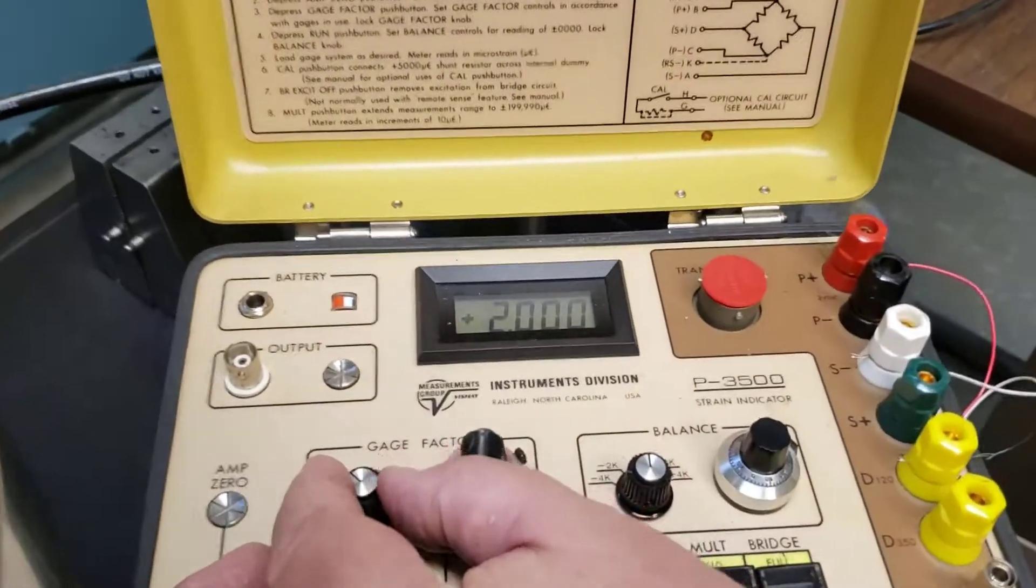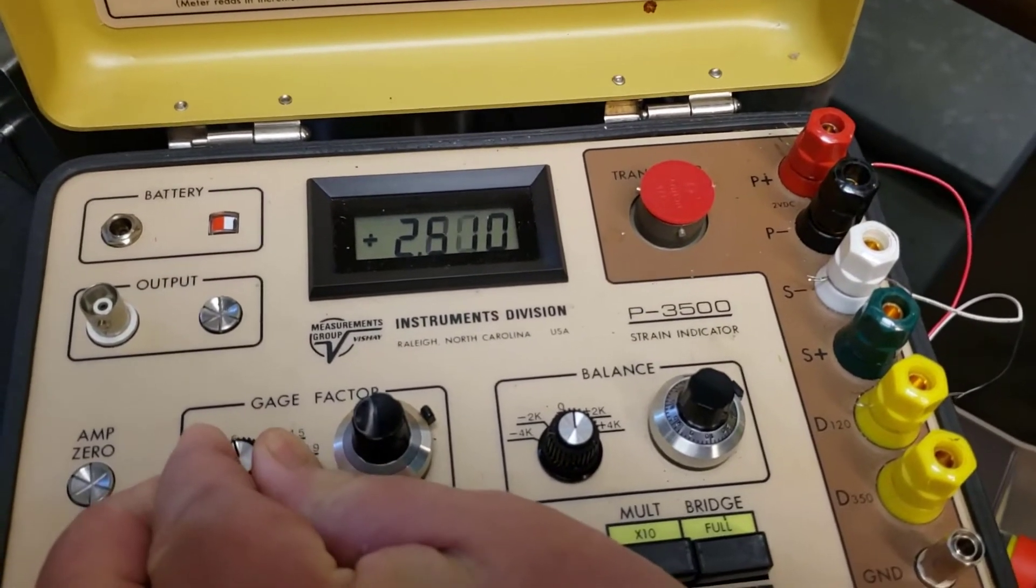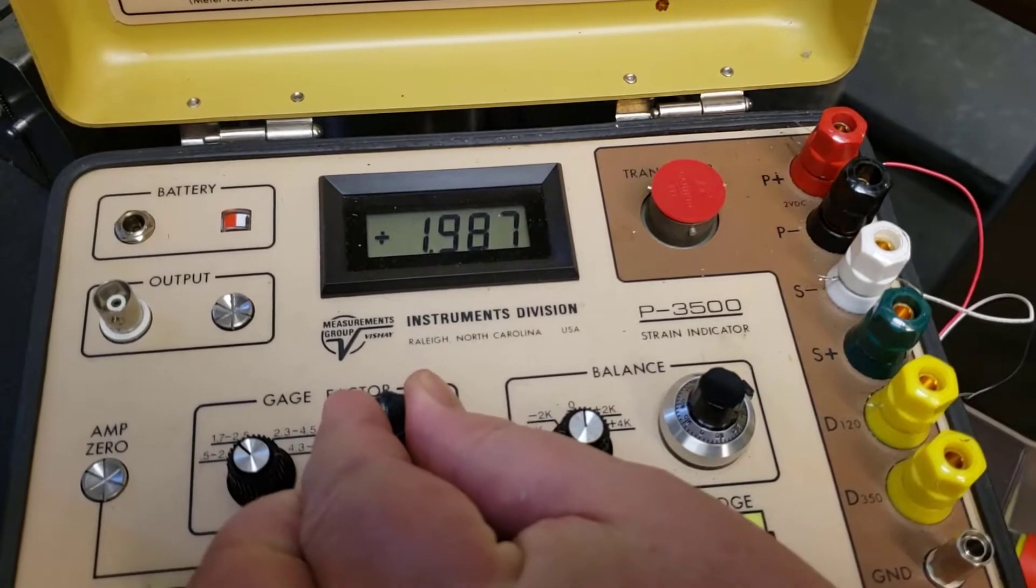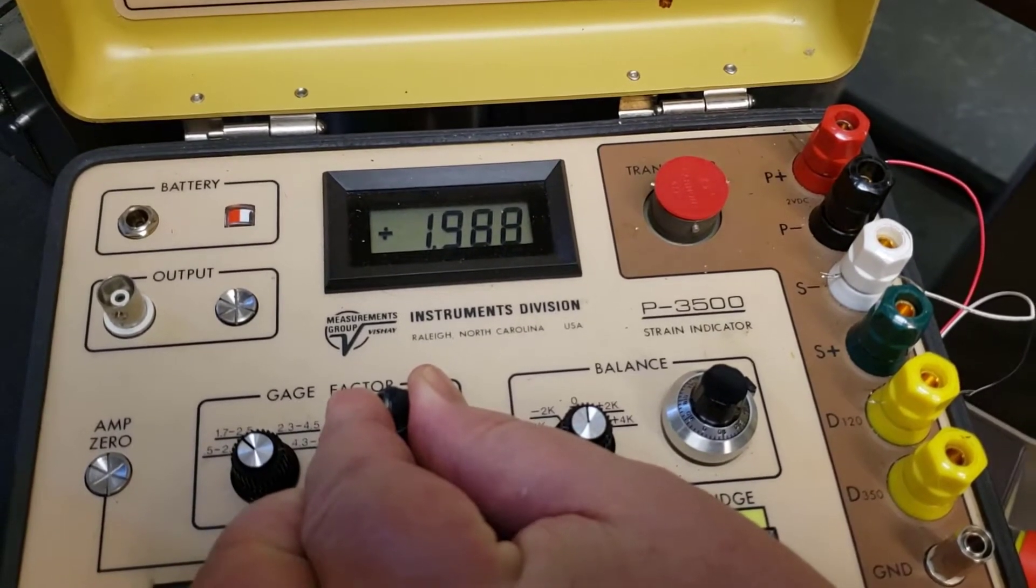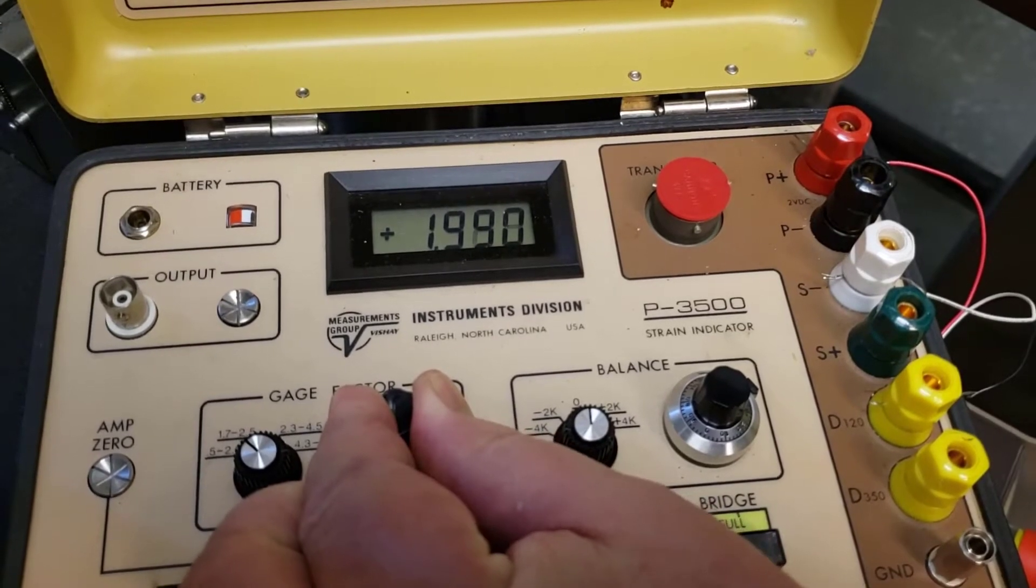This can be adjusted with the gauge factor here. Let me get my other hand to show you, and we can turn that up and down a little bit. You can see, and then some fine-tuning here. Normally these are 1.99, this particular batch.